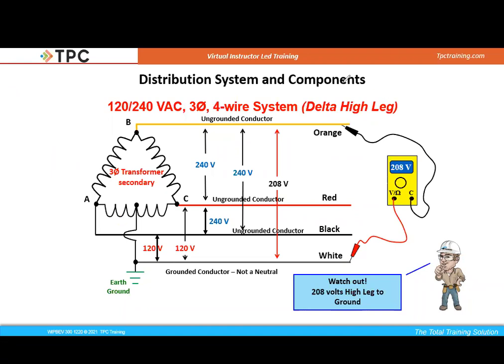And so, just like my other system, if I come from the outside of my energized conductors, phase A, phase B, phase C, then I could definitely have three phase 240 in this system, and very handy back in the 1950s because I could run three phase motors on 240 volts, no problem, and also have available to me 120 volts for receptacles. So it was pretty darn handy, right? But the issue is, you're going to see it here in a second, that when I did want that 120 volts, I had to be very careful about which phases I would use to get my 120 volts.